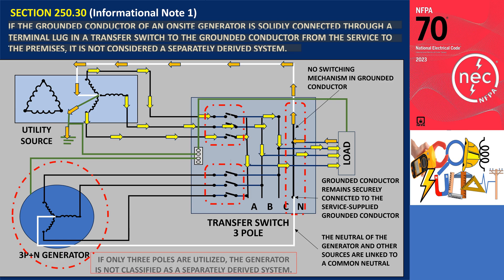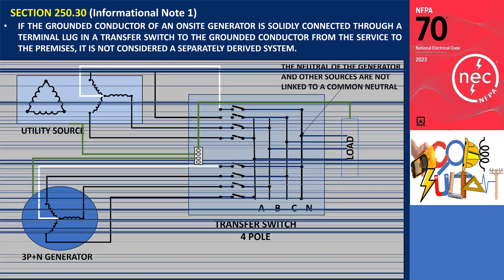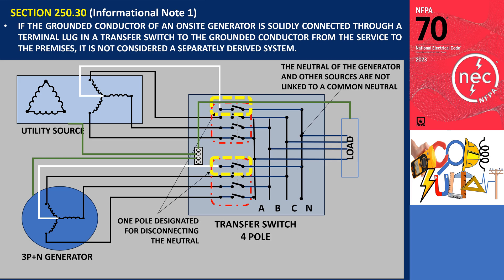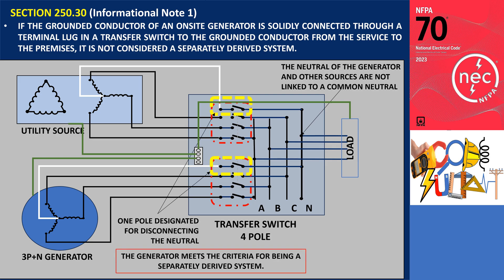If a four-pole transfer switch is utilized, with one pole designated for disconnecting the neutral, then the generator meets the criteria for being a separately derived system.